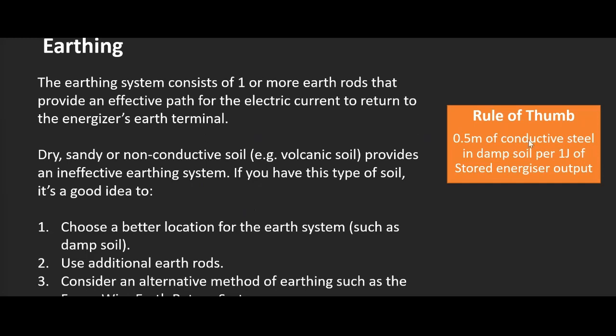As a rule of thumb, you should have 0.5 meters of conductive steel in damp soil per joule of stored energizer output. So if the top 30 centimeters of soil is dry, you need an earth rod probably 1 to 1.5 meters long, to drive in sufficient depth through that dry region to the damp soil below.